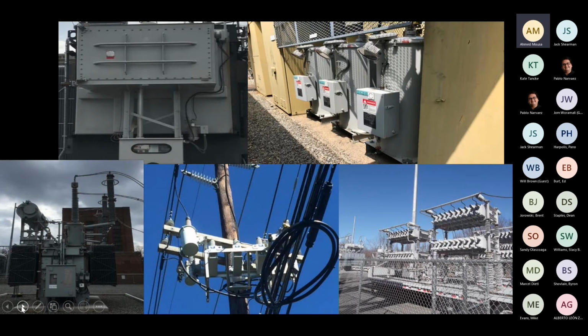On the bottom right, that was a mobile cap bank at a large substation. Bottom middle, that's a cap bank—wherever you travel, you always see cap banks, the easiest, cheapest way to manage voltage. The complete opposite case, which we'll use a lot, is the shunt reactor, like in the bottom left. Especially with offshore wind, we expect to increase shunt reactor use significantly.